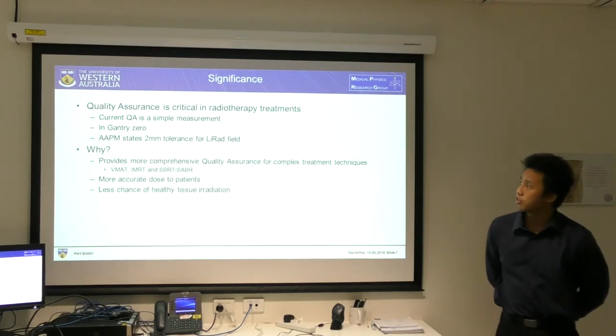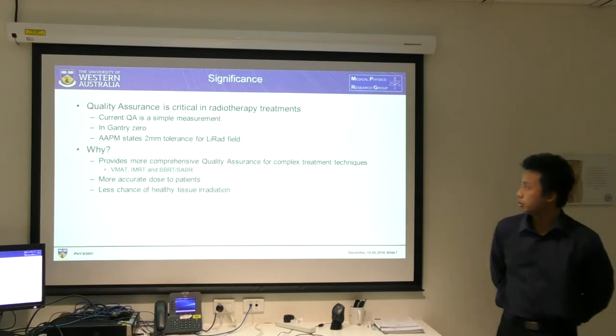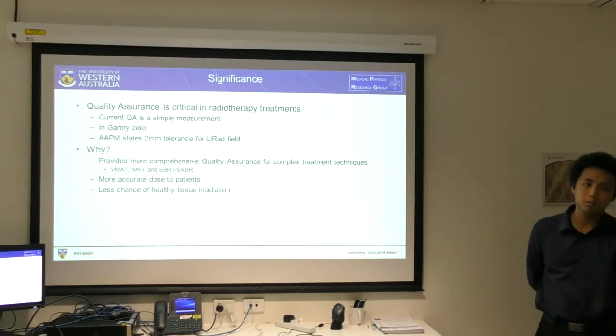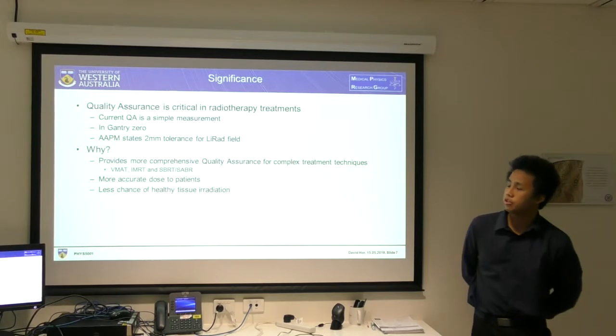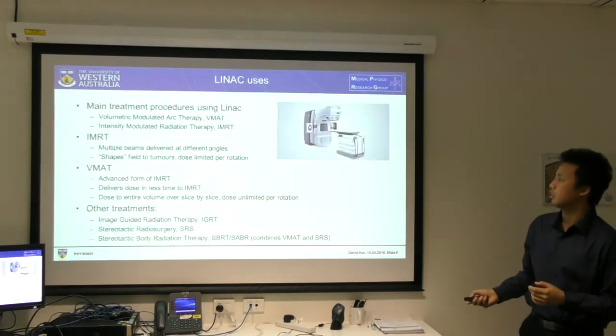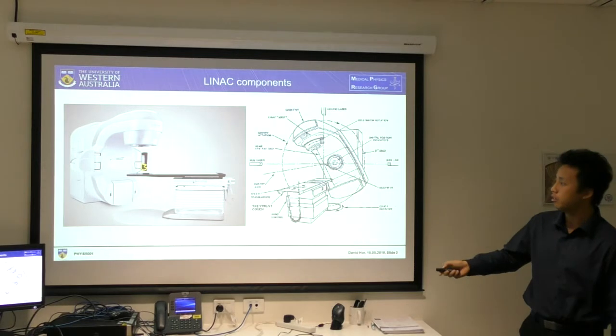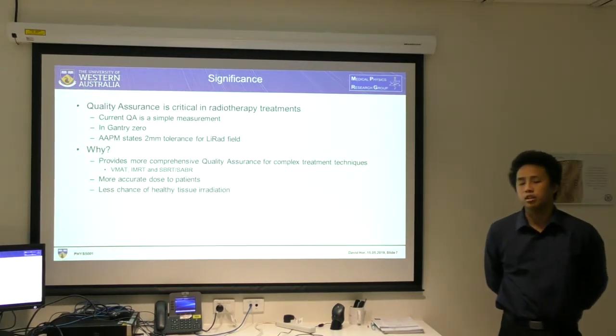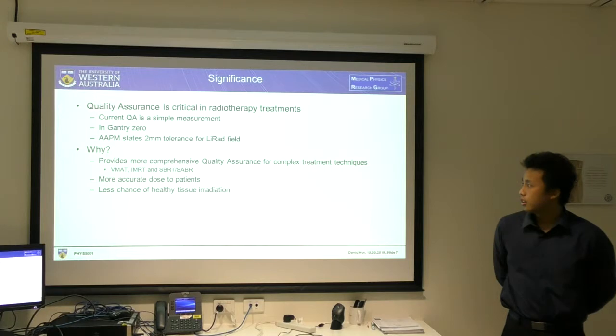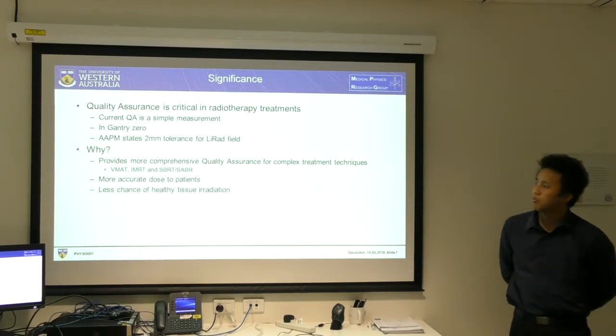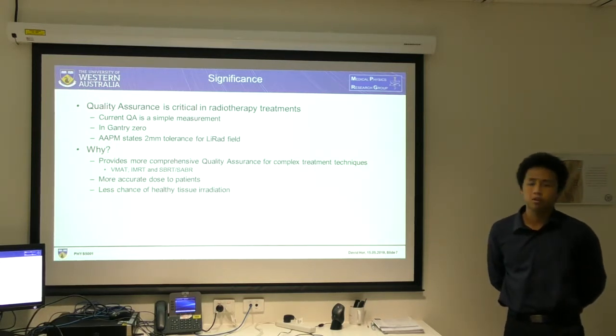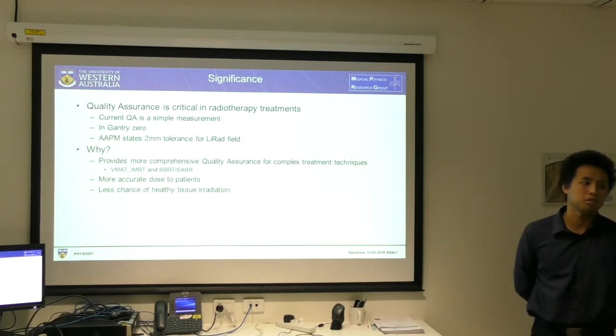My project is mainly quality assurance for the LINAC, and it's very critical because AAPM states there is a 2mm tolerance for light radiation fields. Most current quality assurance methods only conduct the QA of this light radiation field at Gantry 0, and thus don't go into much difference for arc measurements. Measuring in arc is more complex but it helps for VMAT, IMRT, and SBRT, delivering a more accurate dose to patients as it rotates, meaning less chance of healthy tissue irradiation throughout the rotation.